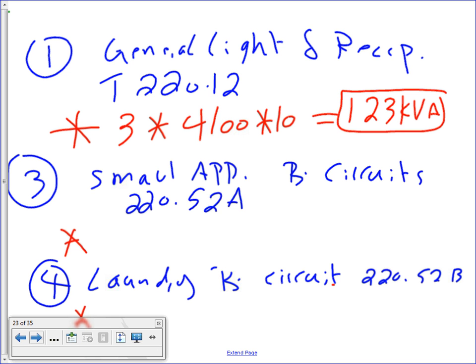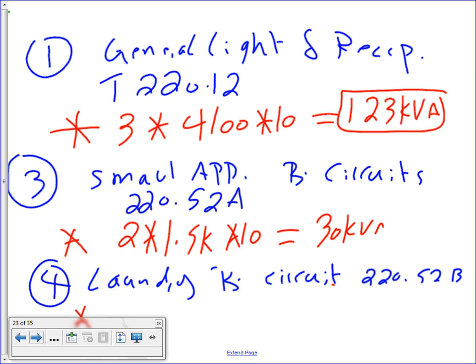Now, Derek, my friend, the 3 is coming from this 220.12 for dwelling. The 4100, that's the square footage of the unit. The 10 because we have 10 units. Straightforward. Then you have to go to small appliance branch circuits. 220.52(A) will tell you every apartment shall allocate 2 circuits, each one of them at 1.5 kVA, and we have 10 of them. So that will get you a total of 30 kVA. Done. 30 kVA.